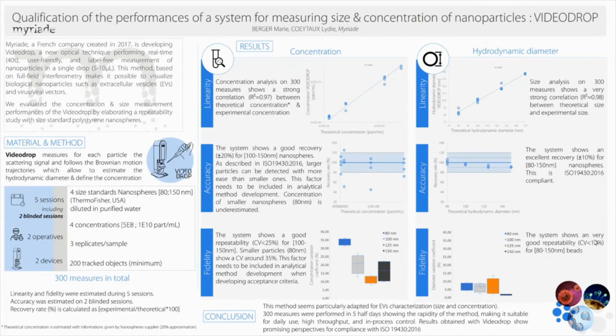300 measurements were performed in 5 half days, showing the rapidity of the method and making it suitable for daily use, high throughput and in-process controls. And also, the results obtained with the Videodrop show promising perspective for compliance with the ISO 19430.